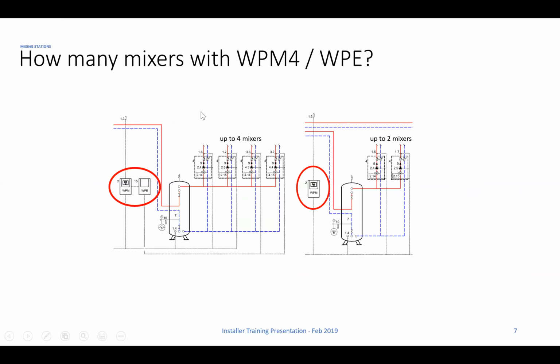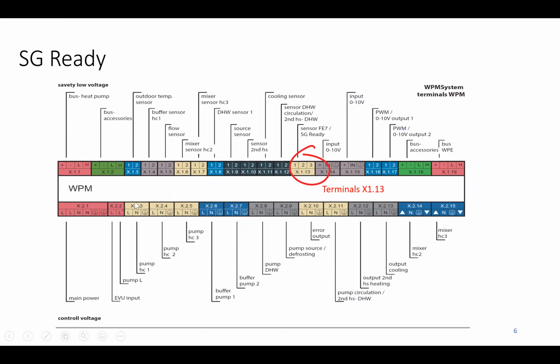Okay, so I've shown this slide quite a number of times before, and probably I'm repeating myself through presentations, but we're trying to make sure everybody's 100% across it. If you have a WPM, you can control up to 3 heating circuit pumps, 2 of those being mixed. Okay, so 3 heating circuit pumps, with 1 being the unmixed circuit because there's no mixer attached to it. There's not even terminals for a mixer for heating circuit 1. Heating circuit 2, a pump and its corresponding mixer. Heating circuit 3 and its corresponding mixer.